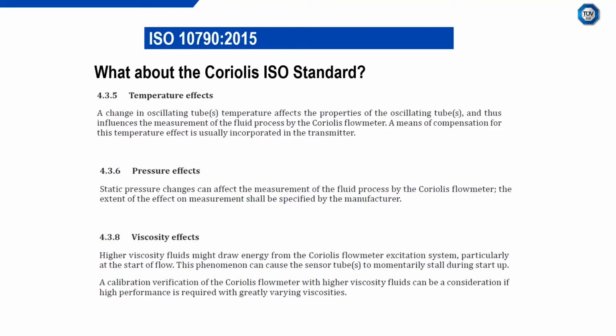It tells you that there could be a pressure effect, and also that there could be a viscosity effect as well. It doesn't tell you too much more. Crucially, it doesn't really tell you how to compensate for these effects. I like to think that the standard should maybe provide more guidance to the end user. So it recommends that you calibrate at conditions if possible and use a traceable correction if required. At present, I don't think the Coriolis ISO standard is overly helpful, hence why I'd like to see it revised with real data for temperature, pressure, and viscosity / Reynolds number effects.